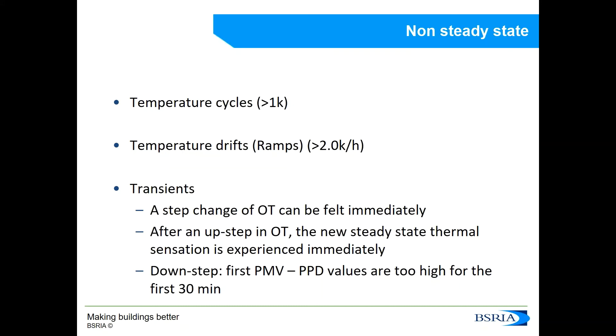Regarding transients, the following statements can be made. A step change in the operative temperature can be felt instantaneously, and after an up-step in the operative temperature, the new steady state thermal sensation is experienced immediately. But following a down-step in the operative temperature, the PMV and PPD values are going to be too high for the next 30 minutes until we acclimatize ourselves to the new thermal conditions.